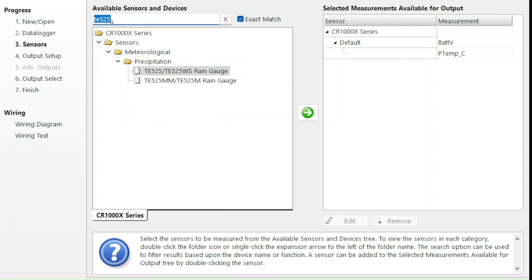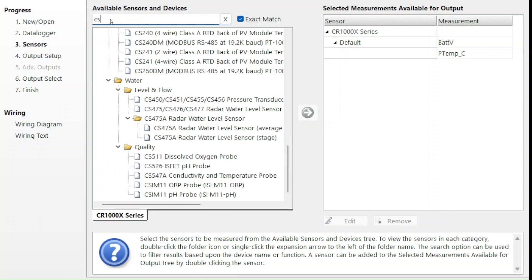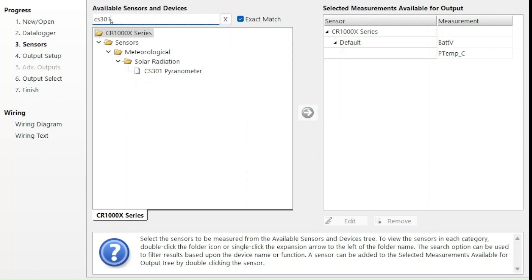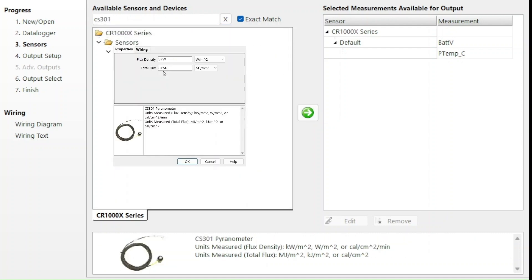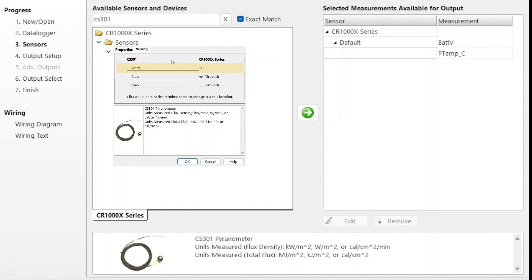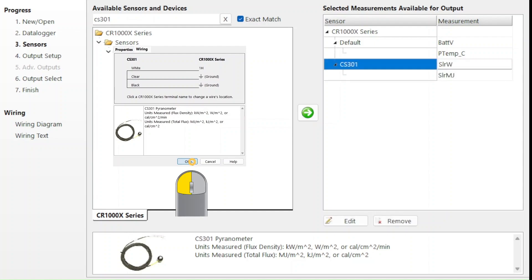Next, I try searching for the CS301 and double click that to open the configuration window. This time, the wiring tab shows me a white wire at 1H and a black wire at ground. This matches the wiring for my station, so I select OK.